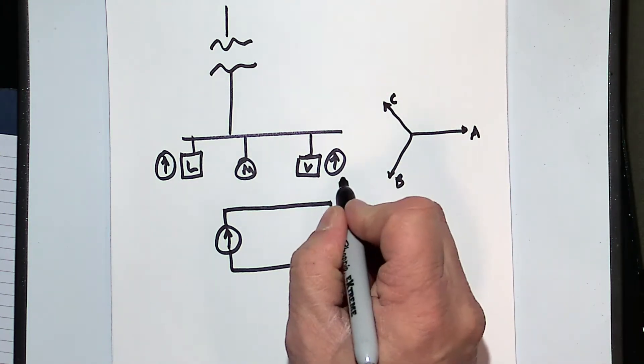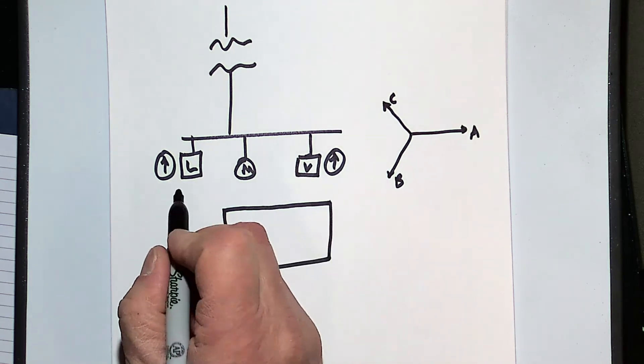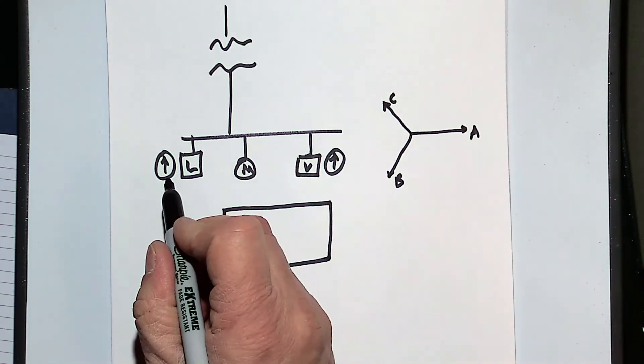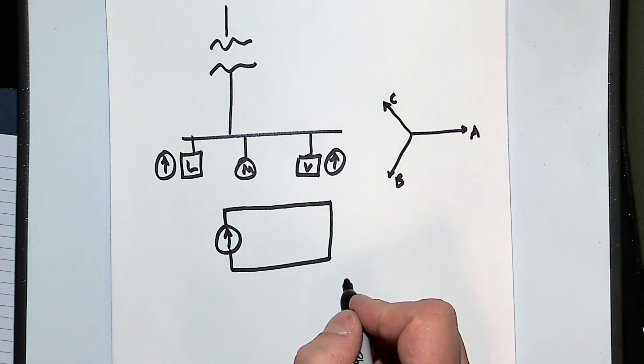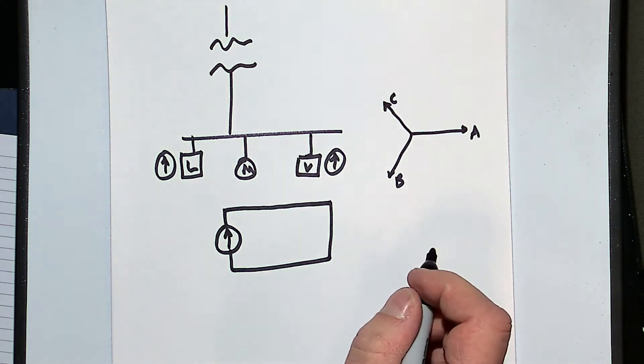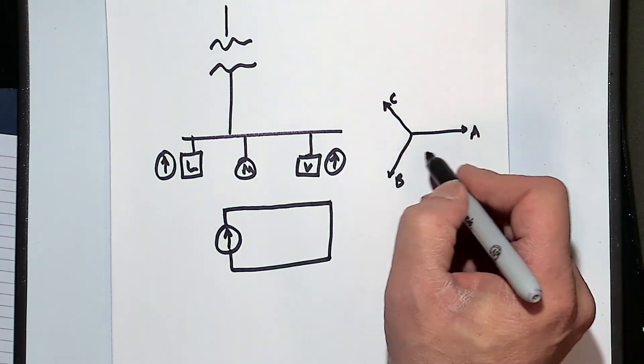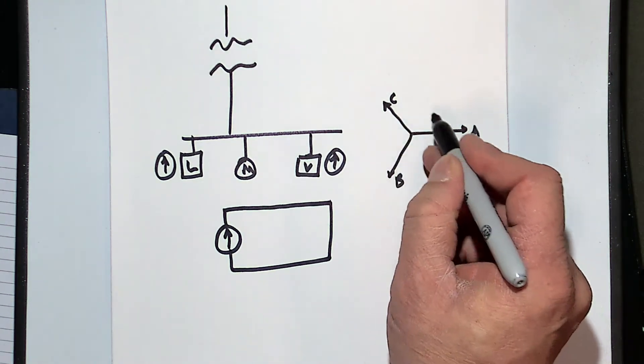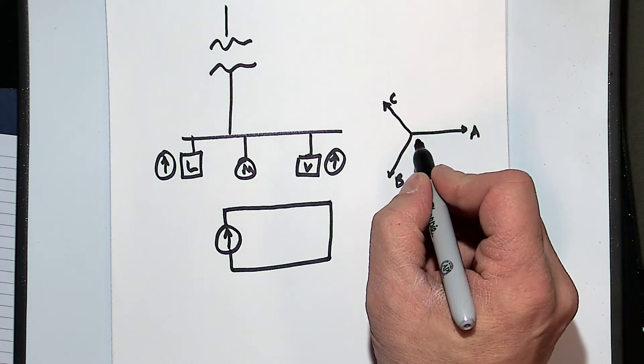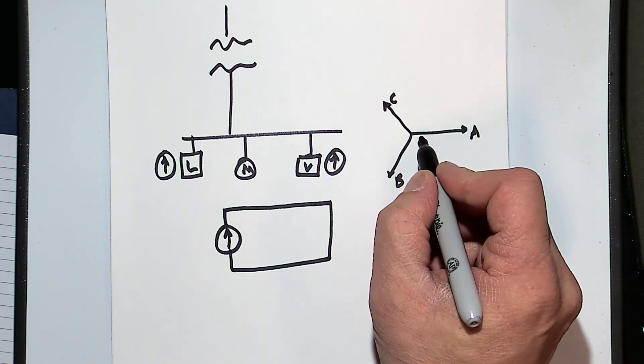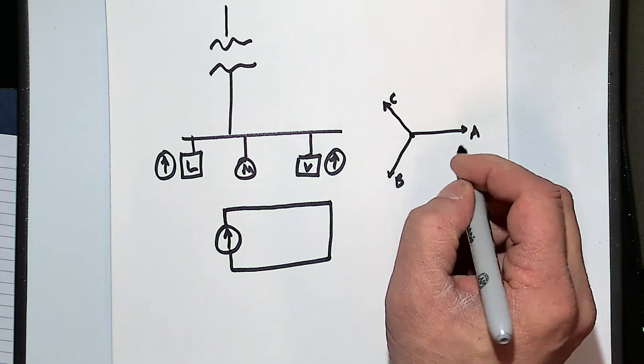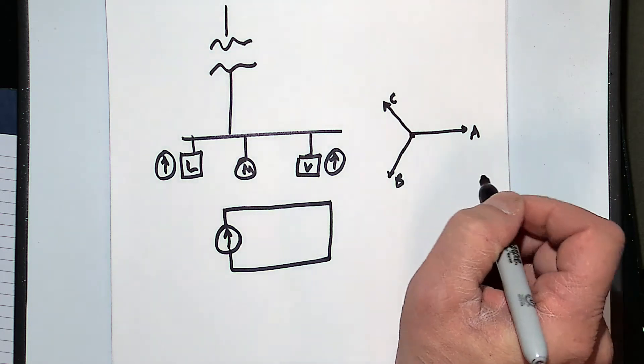That's what happens with three-phase loads. What happens with single-phase loads is it goes out on A for, say, a light, and it comes back on the neutral. You can see that if the loads are balanced, my phase currents and my harmonic currents, for the most part, are going to add up to zero because they're all out of phase by 120 degrees.